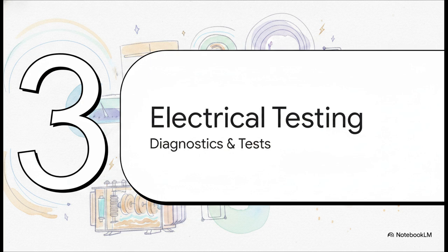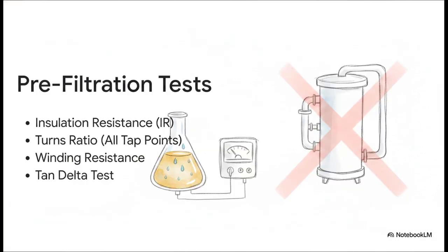Now for Section 3, Electrical Diagnostics and Testing. Okay, once the mechanical parts are totally cleared, we move to the critical electrical tests. Things like tan delta and insulation resistance, which basically measure how well the internal components are shielded from one another. But here's the kicker. These must be done before any oil filtration takes place. Why? Well, if there's any moisture at all in that oil, it'll significantly alter your diagnostic results. You really want to capture that true, worst-case scenario of the insulation's health before you go in and start cleaning up the system.